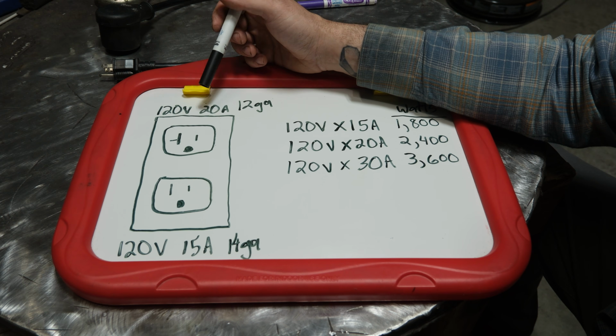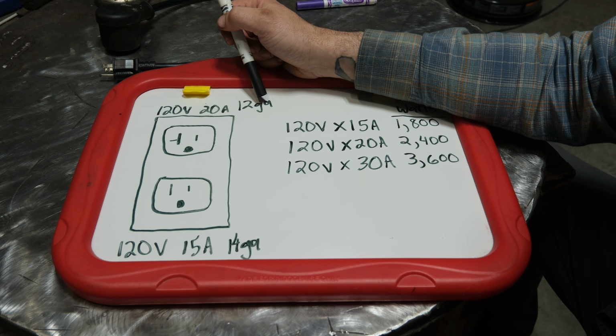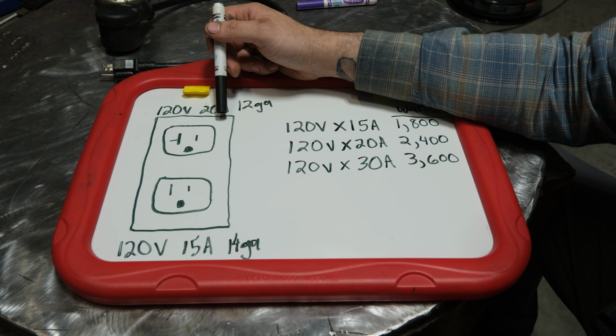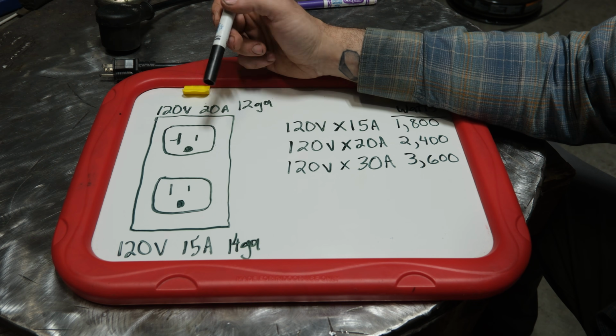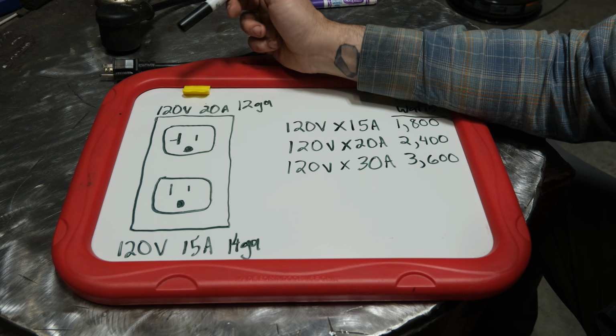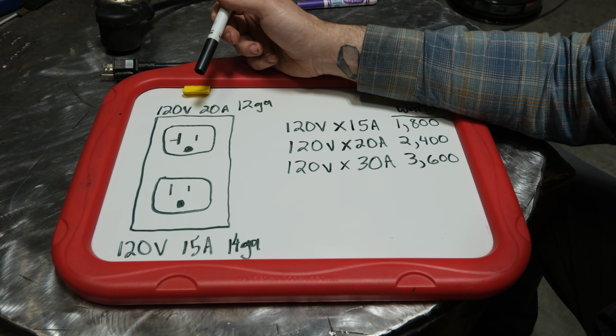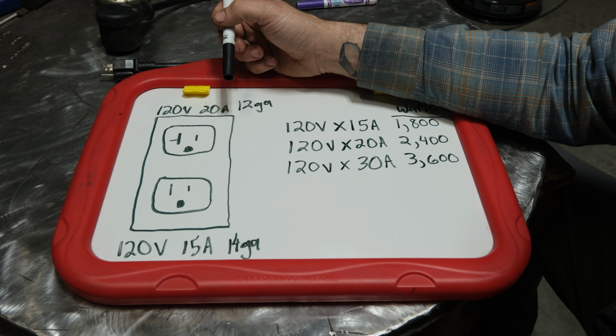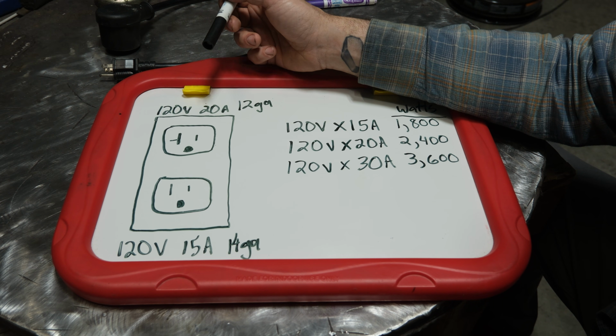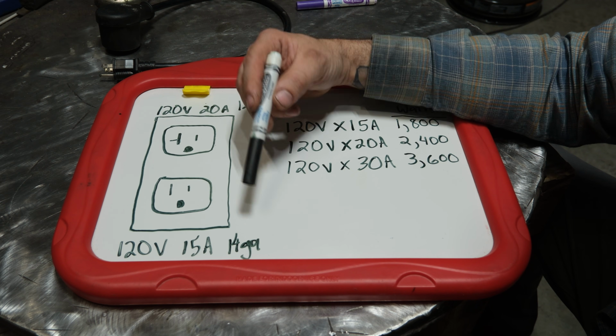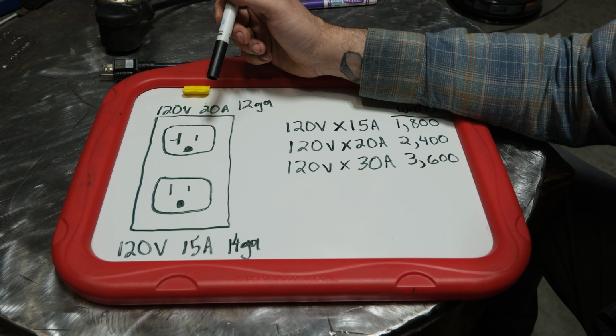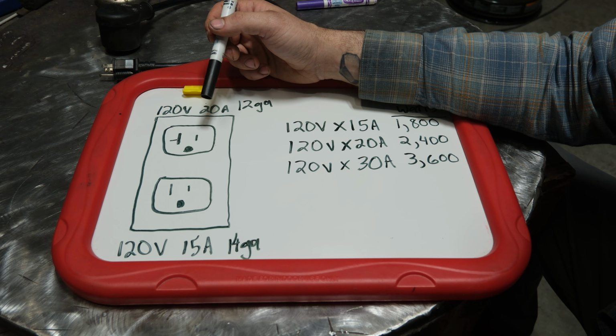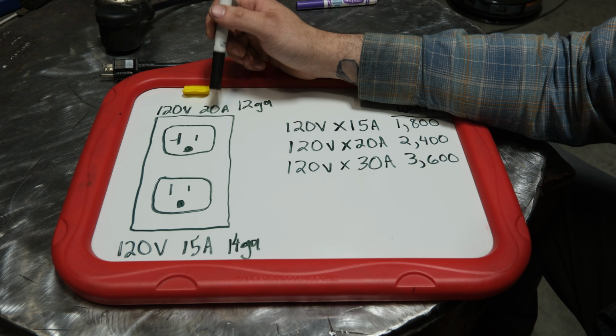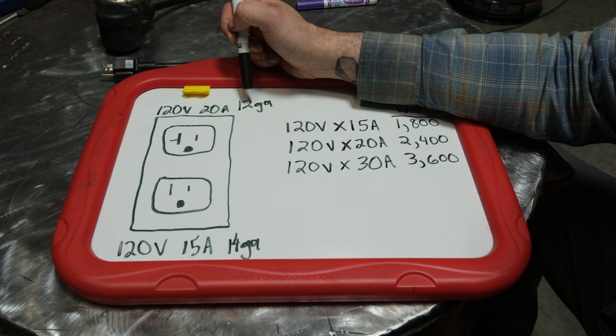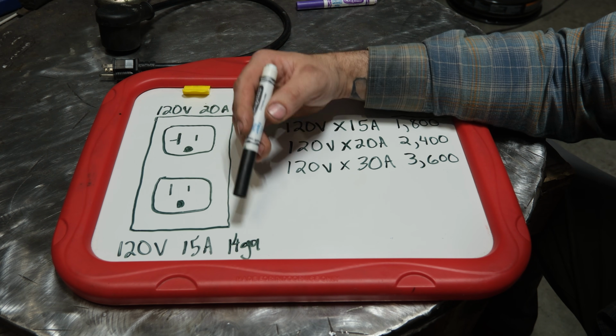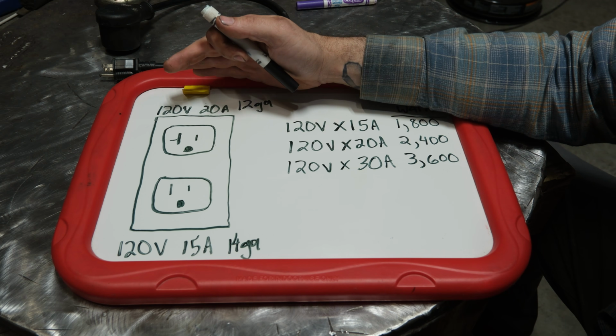Now, speaking also of breakers, you need to have 12 gauge wire wired to a 20 amp outlet. That is code. If you have 14 gauge wire wired to a 20 amp outlet like this, or to a 15 amp outlet, again, you're going to have limitations in how much power you can pull. If for whatever reason you have a 20 amp breaker and 14 gauge wire, that's a big no-no. You could end up melting that wire by drawing too much current. So again, to simplify it, if you have a 20 amp breaker, it should have 12 gauge wire. If you have a 15 amp breaker, it should have 14 gauge wire. Hopefully that all makes sense.